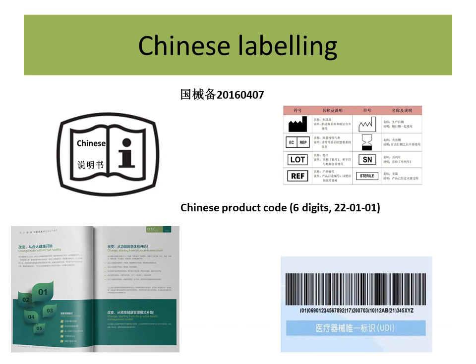Labeling serves to identify a device and its manufacturer, and to communicate information on safety, use, and performance. The typical labeling is instruction for use, product and packaging label, marketing material, country-specific code, unique device identification, assurance code and claims. It is used to provide essential information about its safety, performance, and appropriate use to the user or other relevant persons. Chinese labeling is unique because of its own language Mandarin and some additional requirements.